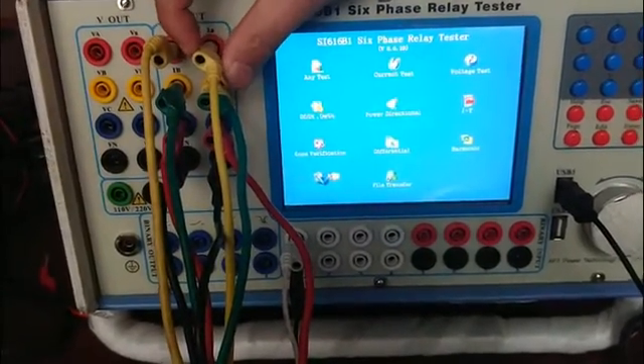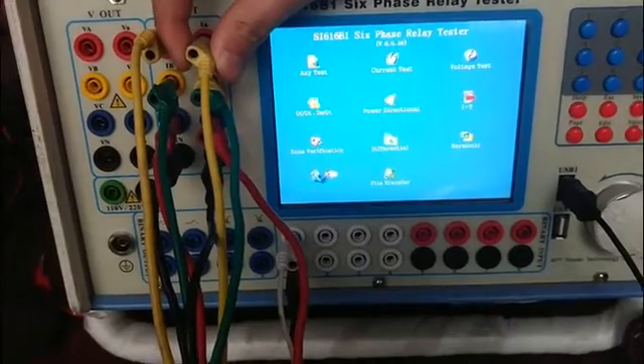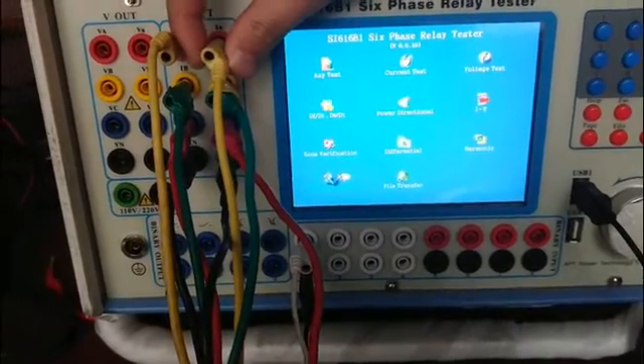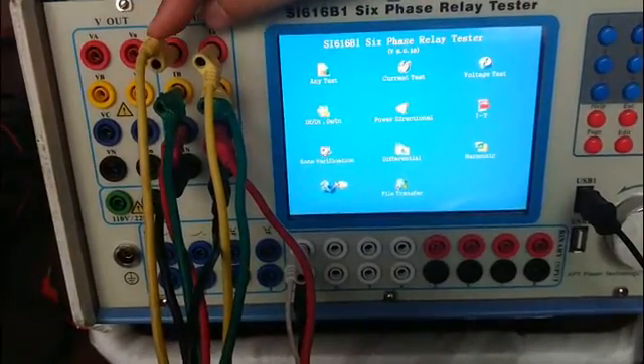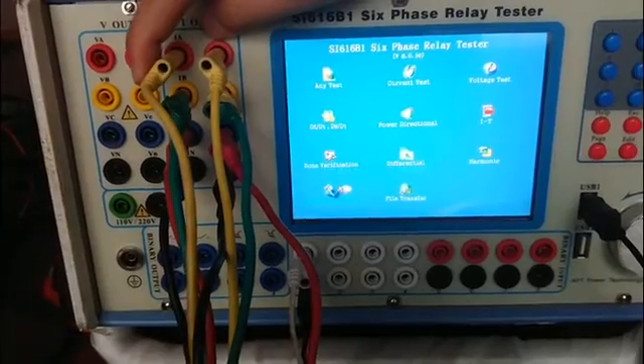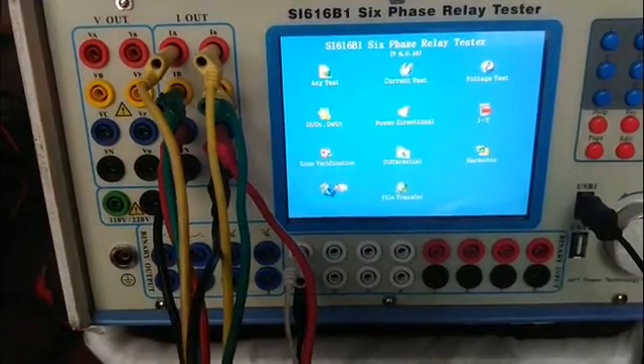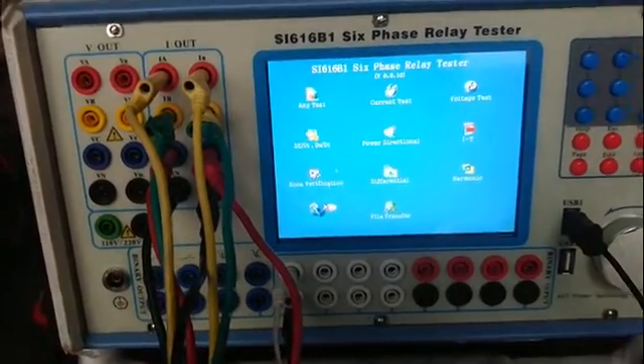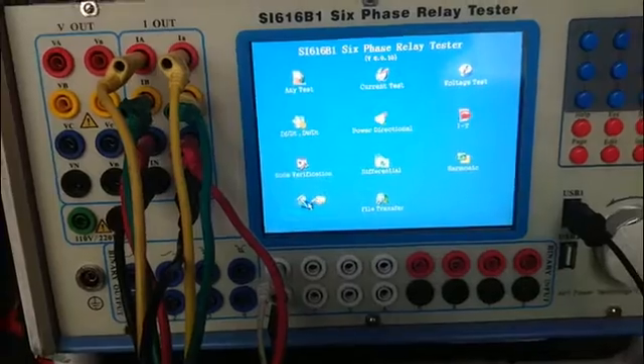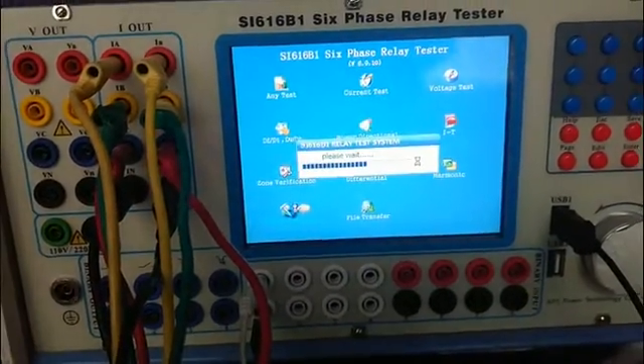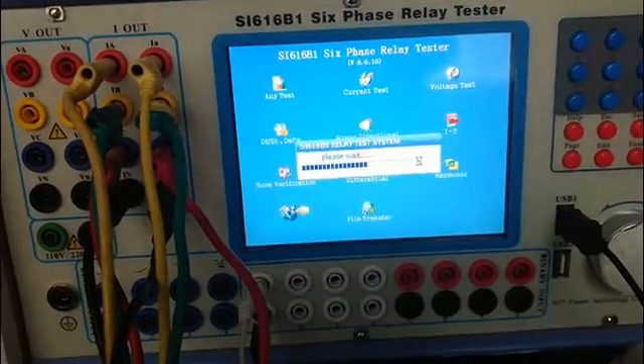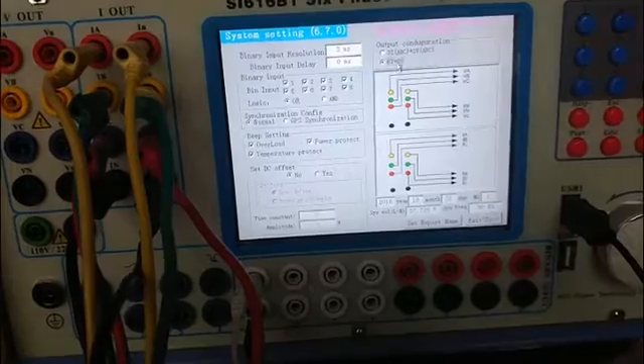Differential relay can be done with only three currents, but it requires the operator be familiar with the protective device and know how to connect wires. Six current is much easier. Now click the system setting to choose six current and six voltage.